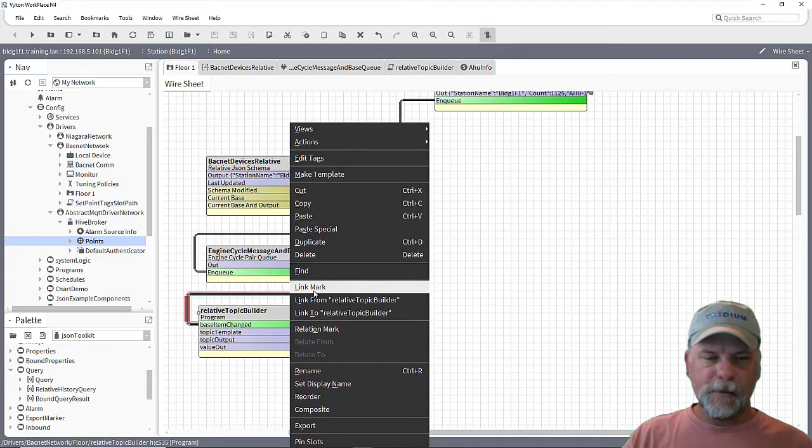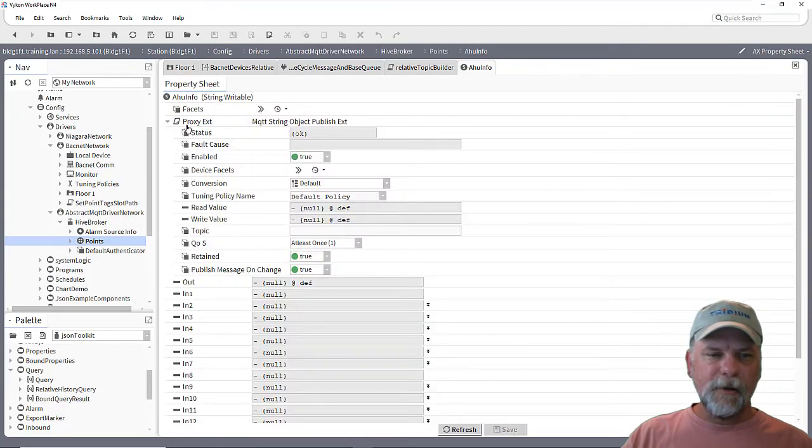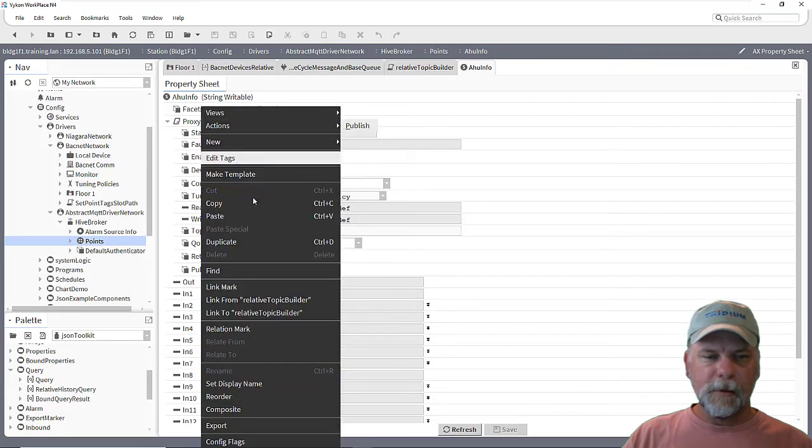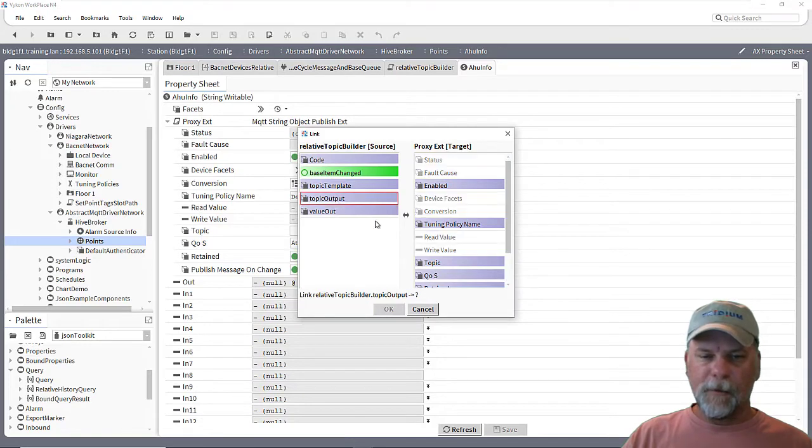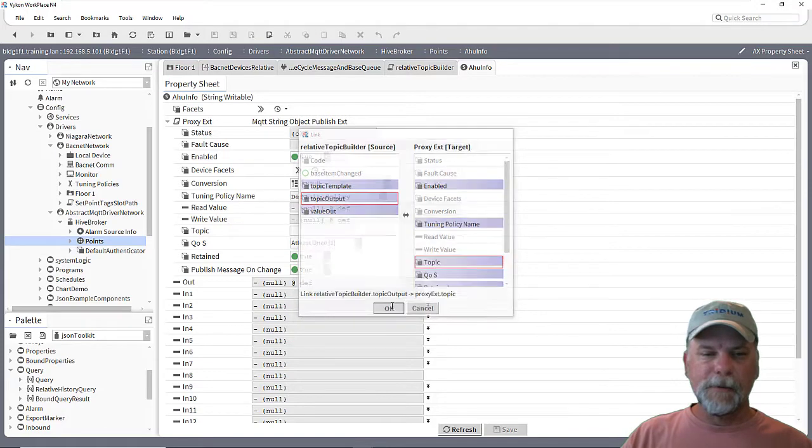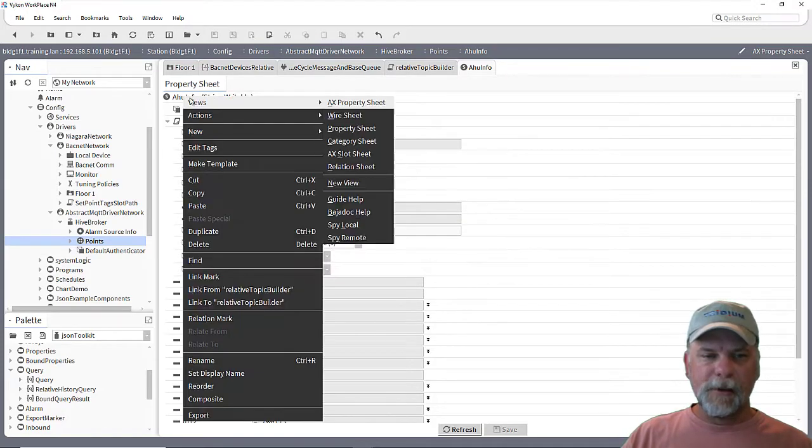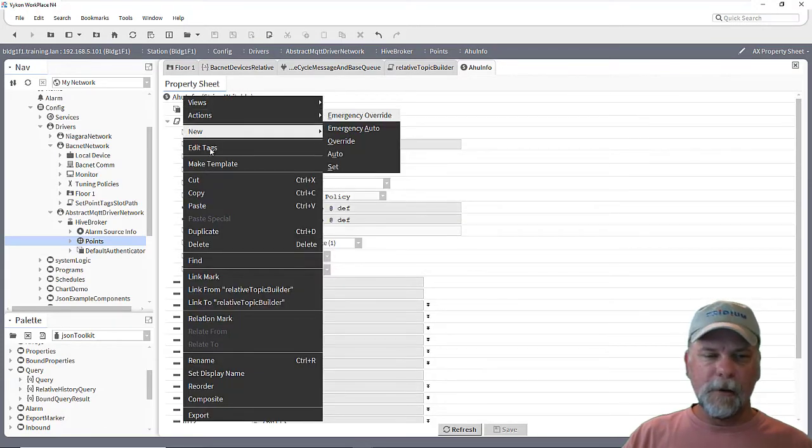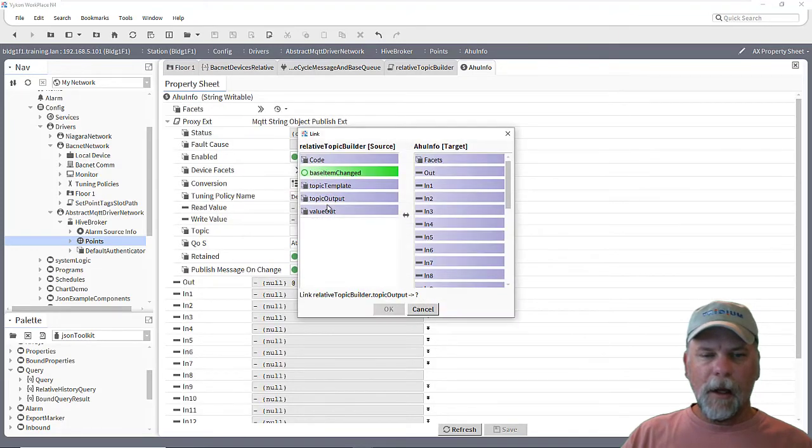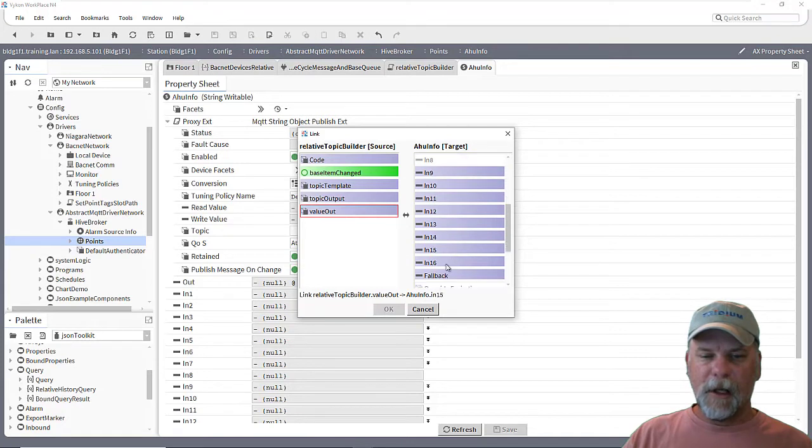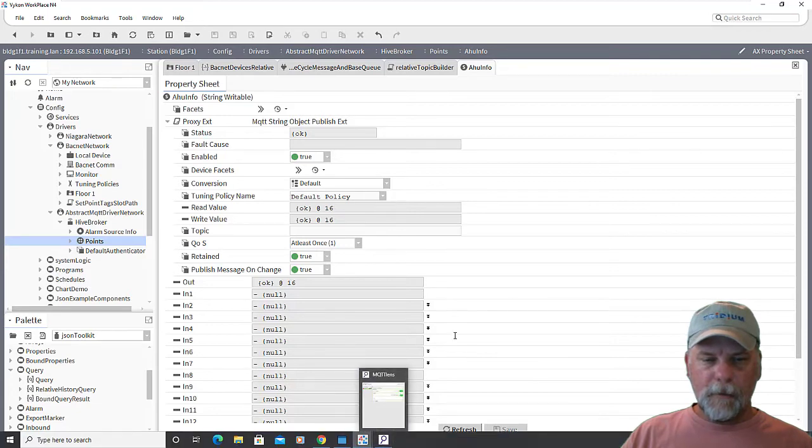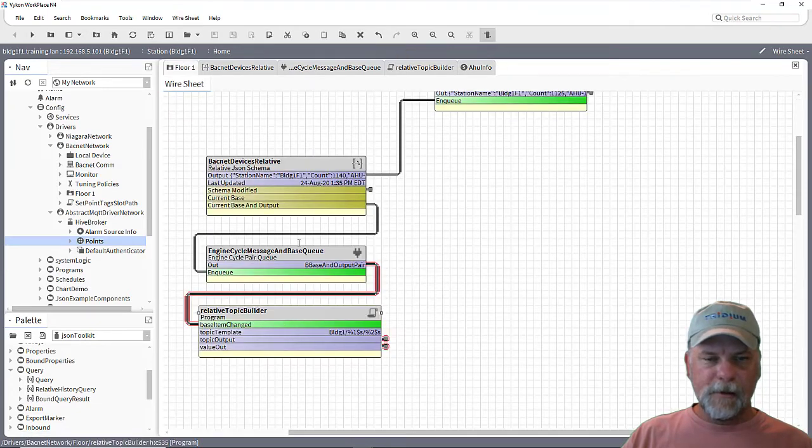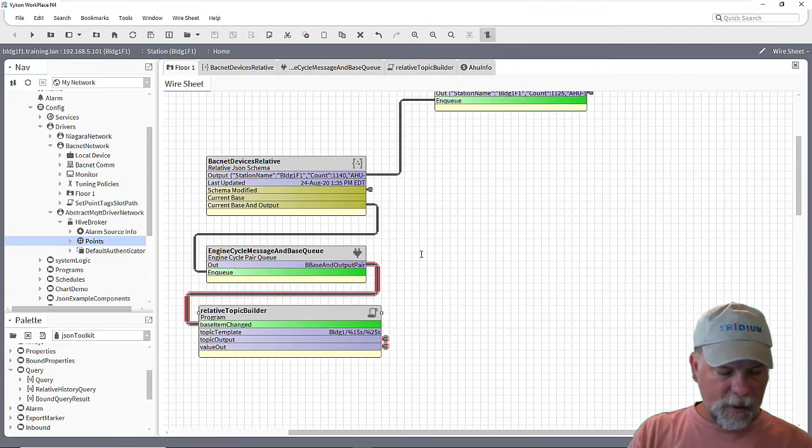What we want to do then is I need to link mark on this relative topic builder here. So I'll right click and choose link mark. And then I need to link on the proxy extension to the topic. So we'll link from the relative topic builder. And I'll pick the topic output and link that to the topic slot on the proxy extension. And then I need to link the actual point value as well. So I'll do the link from again. And we'll pick the value out and decide which slot to link that into there.